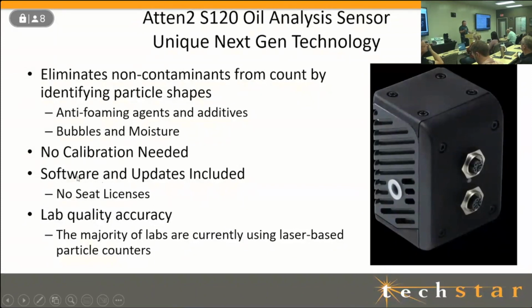So what the sensor allows you to do is not only get an overall particle count for the different size particles that you may see in the fluid, but it's actually able to differentiate if it's additives, moisture in the oil, or different types of bubbles and so forth. And that was always a limitation with laser, is that it included all those different types. Some may be concerning, some may be non-concerning particle count. So you may be looking at a particle count that's much higher with a laser-based technology than what you're actually running. And we're going to show you that.